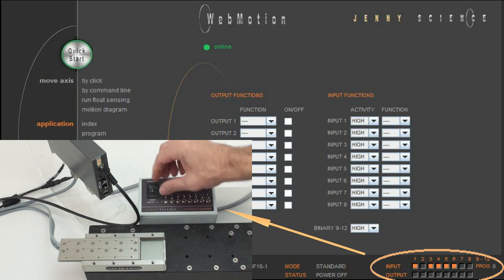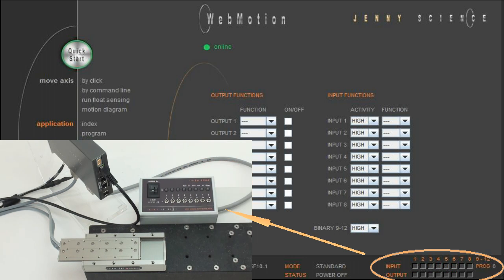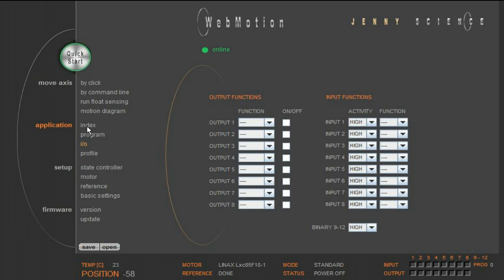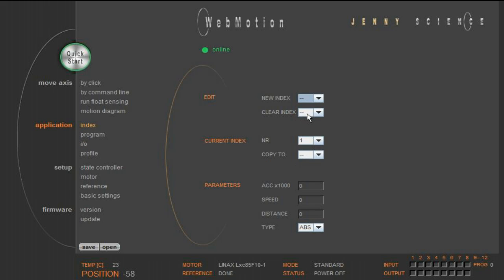To show you the programming of an input function, we create two short indices. The index number contains the acceleration, the speed and the absolute or relative distance of a motion profile. Here we have index 1 with an acceleration of 1 million increment per second square and a speed of 100,000 increments per second with a move to 0.